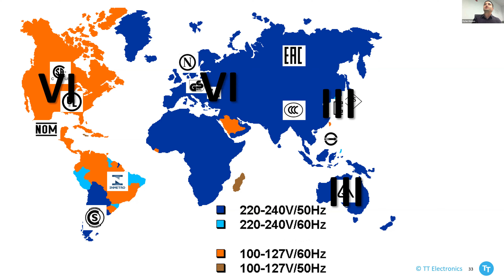So from a technical standpoint, we'll come back to that regulatory stuff in a moment, but when we're talking about different line voltages around the world, most people are probably familiar with the fact that universal rated mains are going to be 100 to 240. So if you take a look at most of your power bricks or wall mount adapters right now, you're going to see 100 volts to 240 volts, 50 to 60 hertz. People are familiar with that. The actual product performance, though, is going to have to allow for 10% deviations on that line voltage and 3 hertz deviations on the frequencies. That gives us what a true universal mains converter input needs to be, which is 90 to 264 volts AC at 47 to 63 hertz.